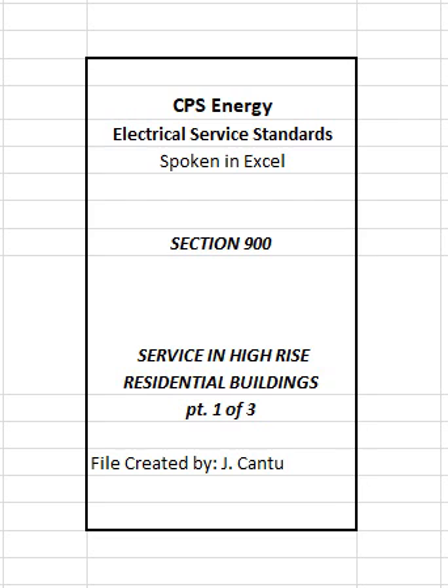902 Customer-owned service lateral and conduits. Customer will be responsible for furnishing and installing the service lateral and conduit, from CPS Energy-owned transformer to their service equipment. Note: where the service lateral is to be installed to service equipment located indoors, conductors shall be installed in a manner that will render them outside of the building and shall terminate immediately upon entering an electrical room approved by CPS Energy. Refer to definition of conductors outside of building.